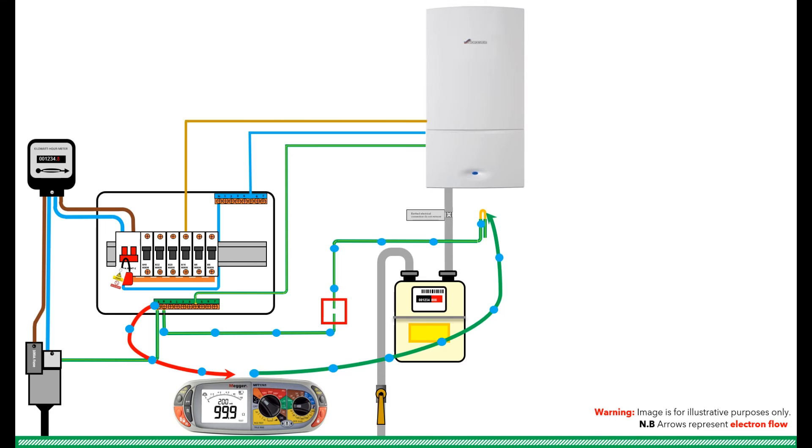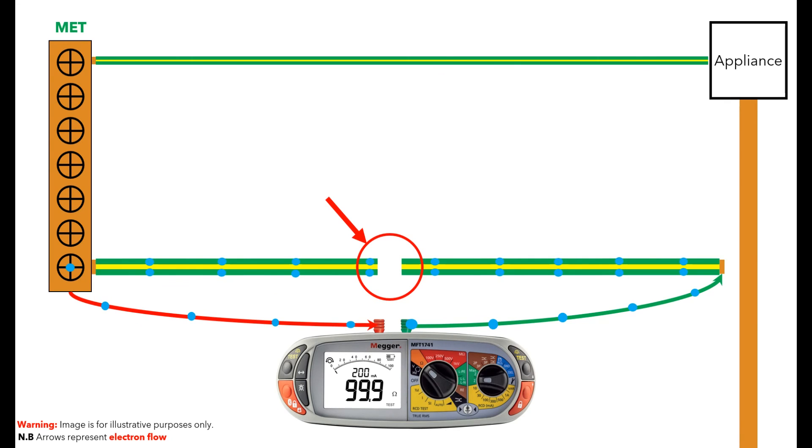If you had a break in the cable, the electrons would not flow as there is no other way for the electrons to get back to the MET, and you would get an out of range reading on your low ohm resistance tester greater than 99.9 ohms. The simplified model would look like this. As you can see, the circuit is now completely broken and the electrons cannot flow, so the meter displays an out of range test reading.